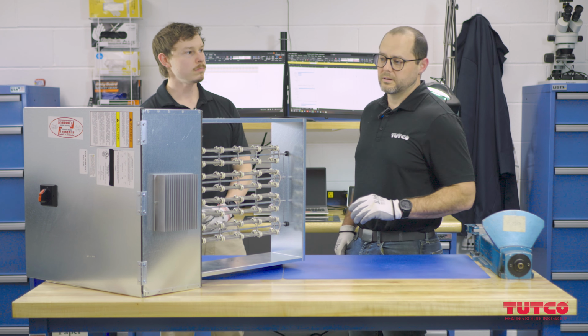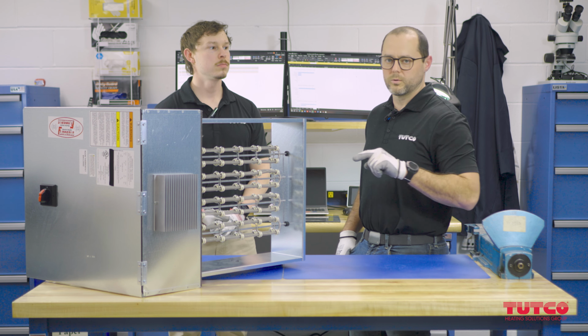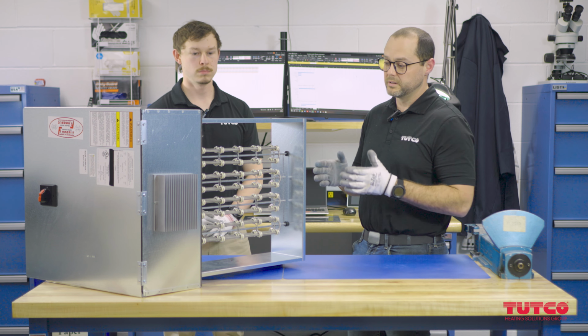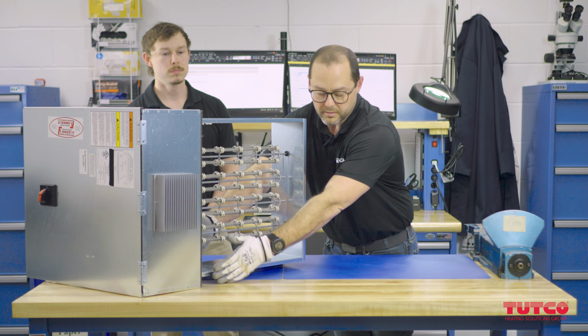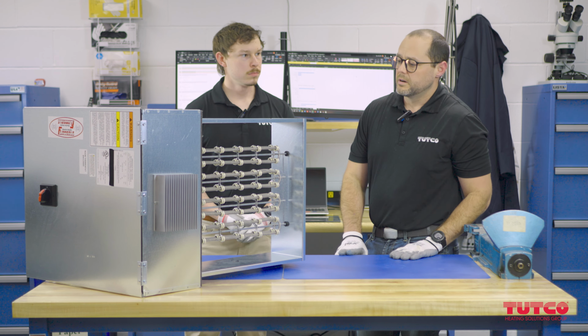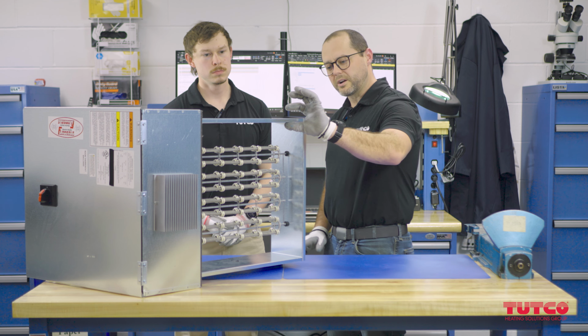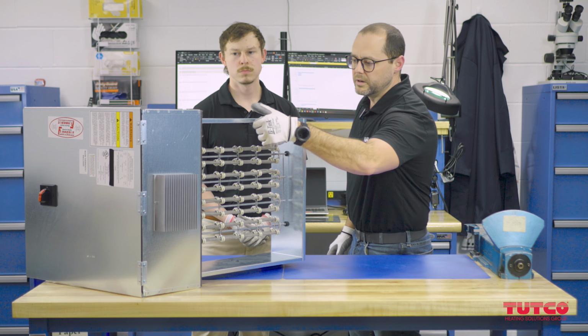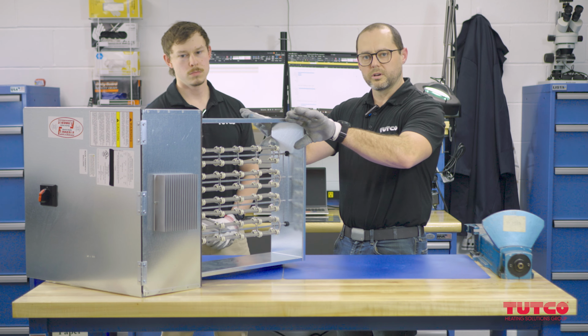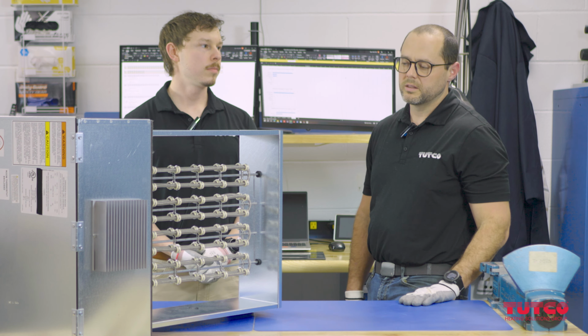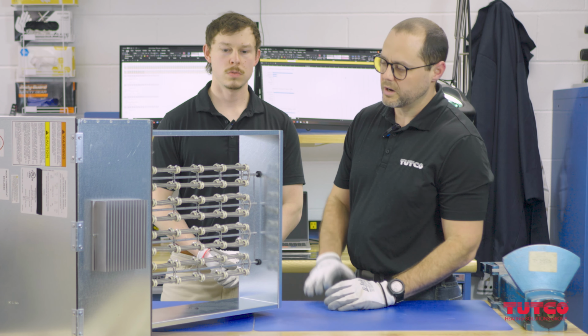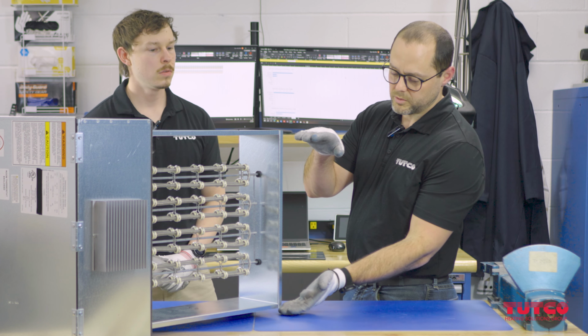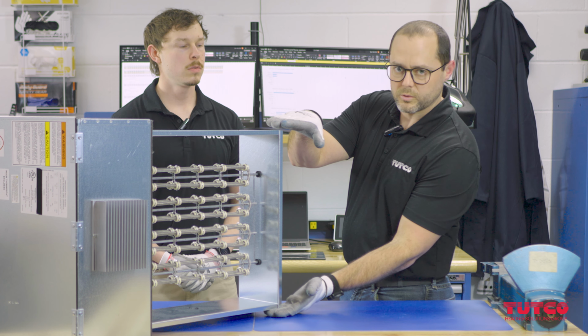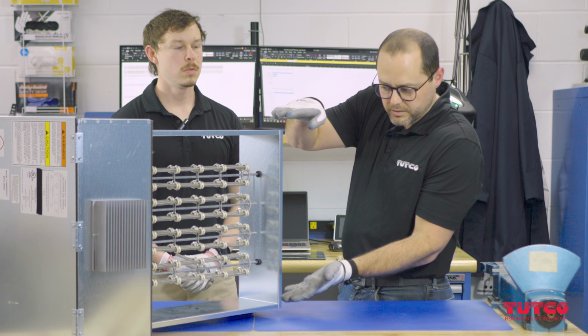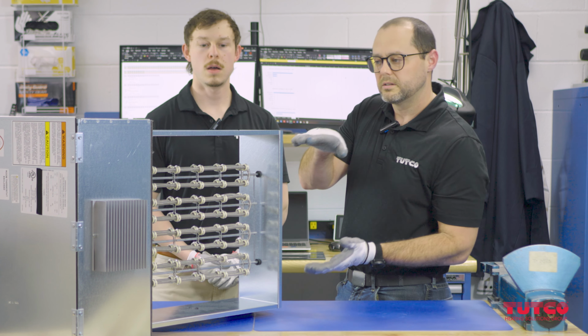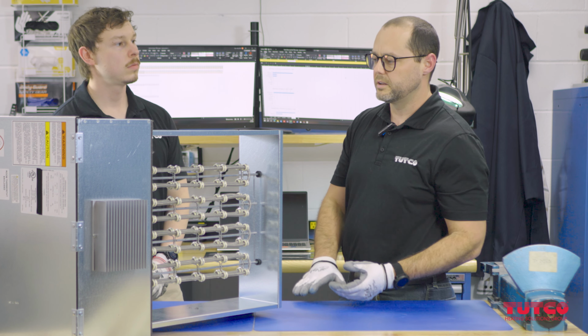Slip-in allows you to cut a hole in one side of the ductwork and then slide this portion of the heater into that area. A flange mount would have wider flanges in this area, allowing you to bolt your ductwork up from either side. So the idea behind sizing on slip-in and flange mount is: for slip-in, you give your actual duct size, and the heater is going to be slightly undersized to be able to slide into the inside of that ductwork.